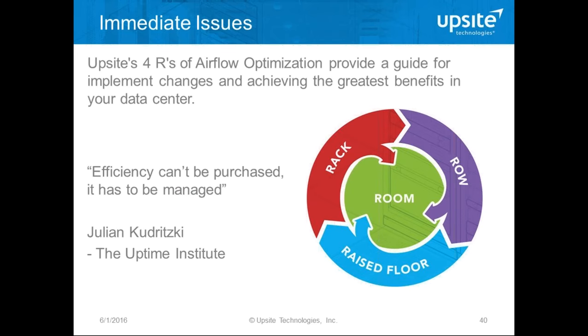What we can learn is that there's no single answer. As Julian Kudritzki of the Uptime Institute put it: efficiency cannot be purchased — it has to be managed. You can't buy full containment, install it, and expect to have an efficient operation. I've been in computer rooms that installed full containment and, although IT equipment may have run adequately, they did not realize the benefits of improved airflow management because they hadn't made adjustments at the room level.